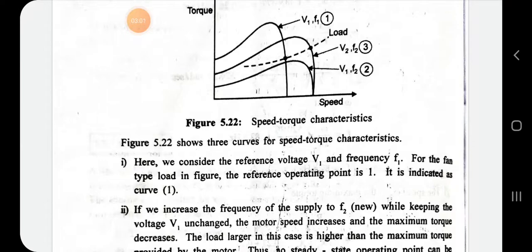Consider reference point one, where voltage is V1 and frequency is F1 — this is for a fan-type load. The reference operating point is indicated as curve number one. Now if I increase the frequency to F2 while keeping voltage constant at V1, the motor speed increases but the torque decreases.